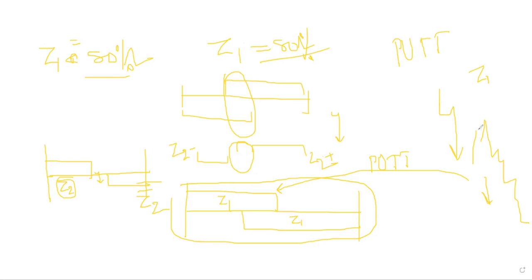Now a severe fault occurred. Due to the severe fault, the calculated impedance is very high, not 80% in this case, so it is leading to zone 2. But actually the fault occurred here only. Due to the arc fault resistance, it is not showing in zone 1, it is showing in zone 2 for this. Similarly, for this one it will also happen. In both cases, both relays are seeing the fault in zone 2.